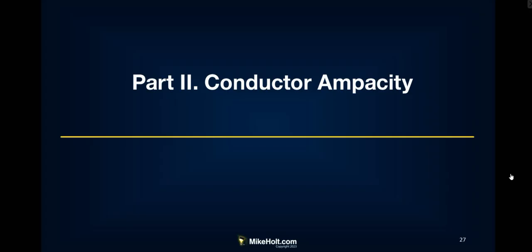I'm going to pick up in one of the modules that is Article 430, and if you look in your code book, Article 430 is going to be motors, motor circuits, and controllers. So I wanted to barely just pick out a section here and talk about conductor ampacity. I believe, if I can get to it, maybe overloads. Typically what we're sizing when we're talking about motors, for the installer, is your conductors, your short circuit and ground fault protection, and overloads. And there's a lot of variety to that. So I'd like to pick out this one section and discuss it.